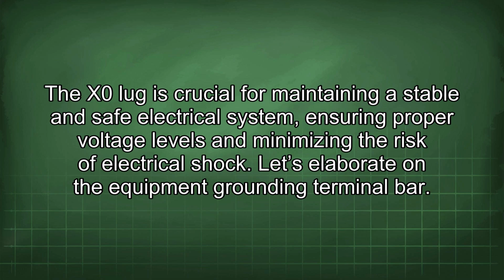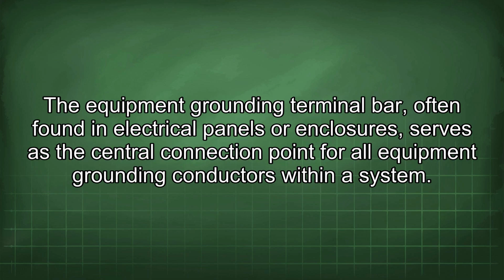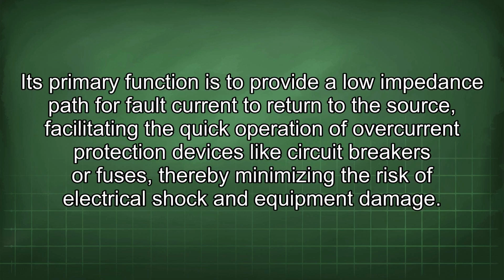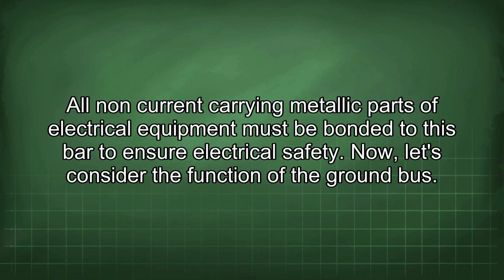Let's elaborate on the equipment grounding terminal bar. The equipment grounding terminal bar, often found in electrical panels or enclosures, serves as the central connection point for all equipment grounding conductors within a system. Its primary function is to provide a low impedance path for fault current to return to the source, facilitating the quick operation of overcurrent protection devices like circuit breakers or fuses, thereby minimizing the risk of electrical shock and equipment damage. All non-current carrying metallic parts of electrical equipment must be bonded to this bar to ensure electrical safety.